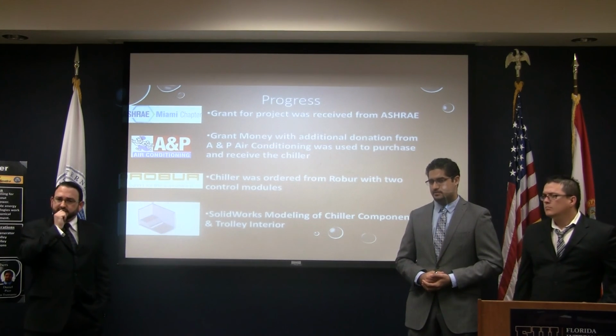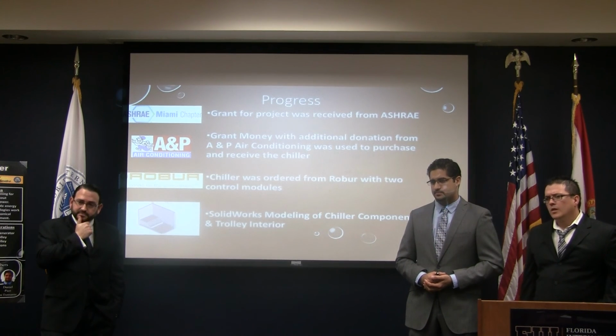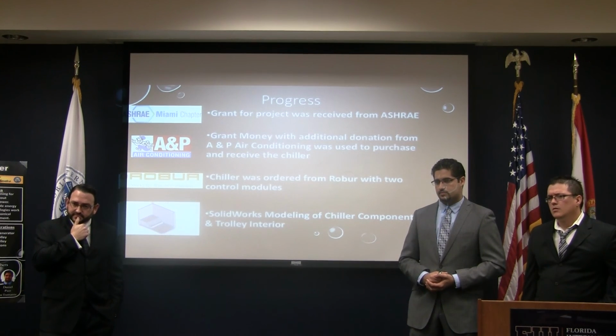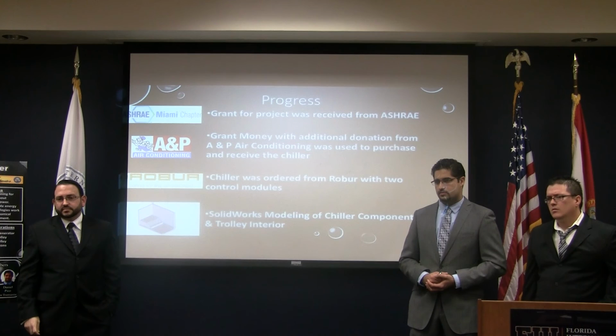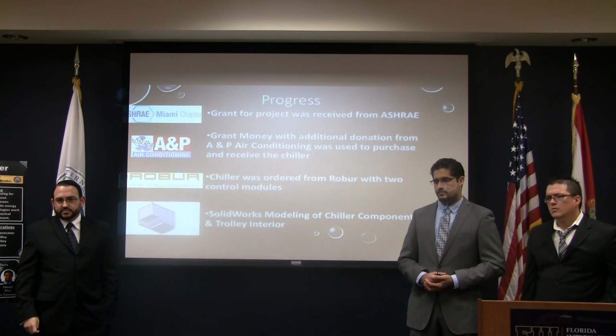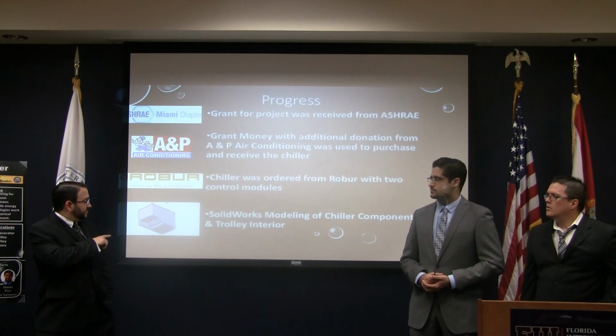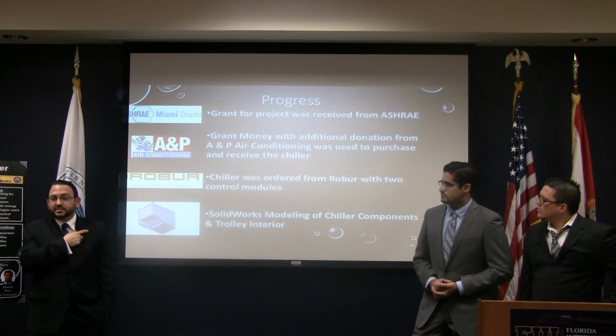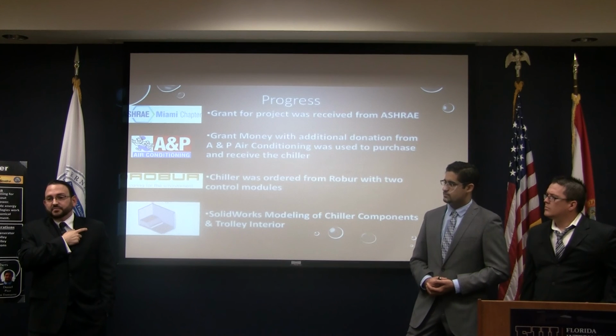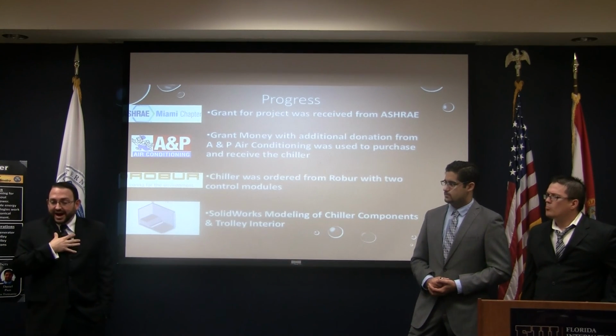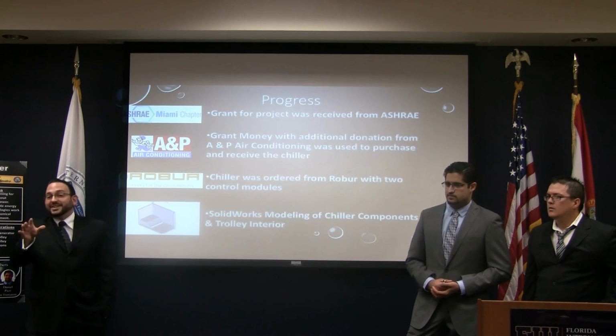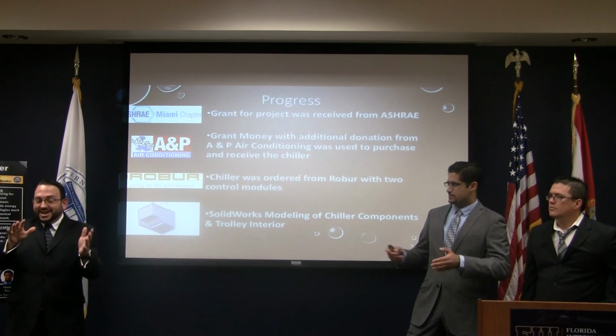Another reason I ask is how you transfer the gas — those hoses need some flexibility to avoid a vibration fracture. You've got an exhaust pipe coming out the back of the trolley and a natural gas source, so you've got a nice fire potential. That said, because it's an absorption chiller, we don't have a vibrating compressor, so our components don't produce the same vibrations as a standard air conditioner by themselves. That's only half the problem, but we did eliminate half of it.